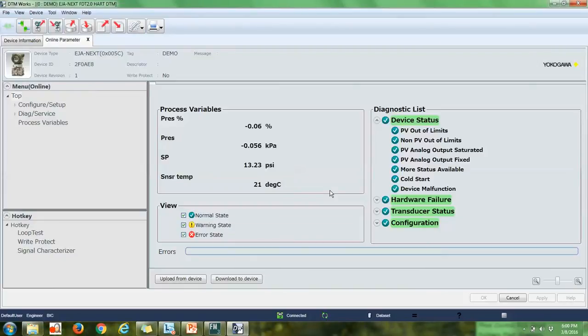So I've got the main menu here for the transmitter. You can see we've got our process variables. These are updated every few seconds to show you your pressure percentage, so percentage of span, and what the actual pressure reading is. So that's differential pressure, and the static pressure. What's unique about Yokogawa's DPharp sensor is that it can measure DP and static pressure simultaneously from one sensor. So we've got that as well. And then also sensor temperature, so the temperature of the sensor inside the capsule. That's just a diagnostic.